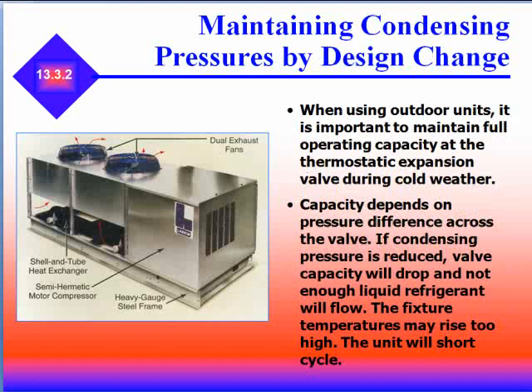When using outdoor units, it is important to maintain full operating capacity at the thermostatic expansion valve during cold weather. Capacity depends on the pressure difference across the valve. If condensing pressure is reduced, the valve capacity will drop and not enough liquid refrigerant will flow, and the fixture temperatures may rise too high, causing the unit to short cycle.